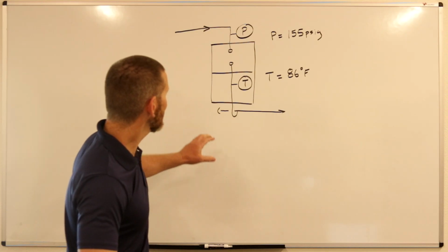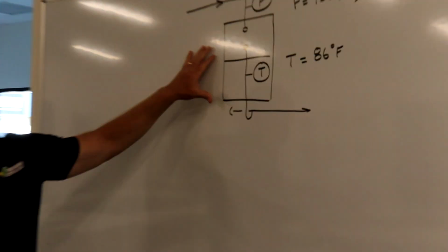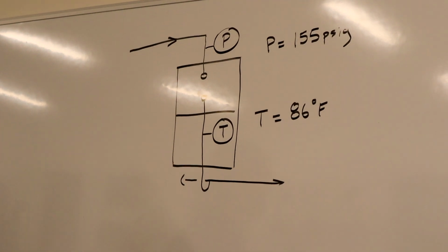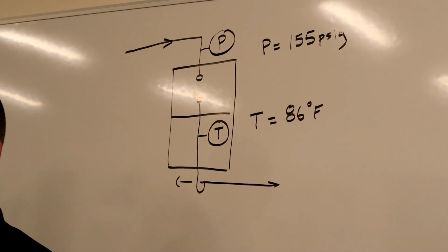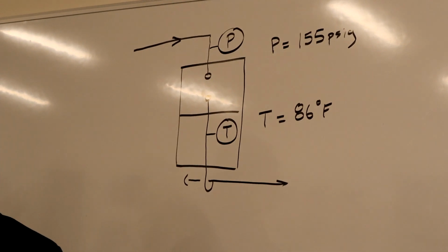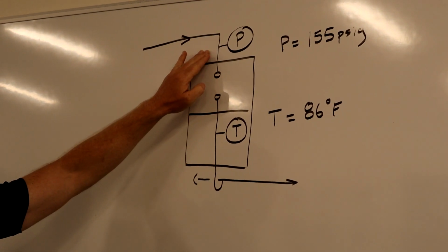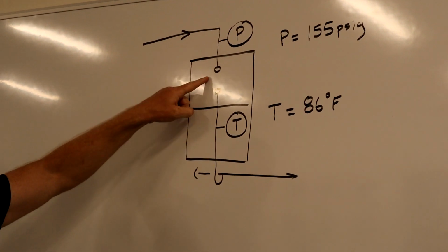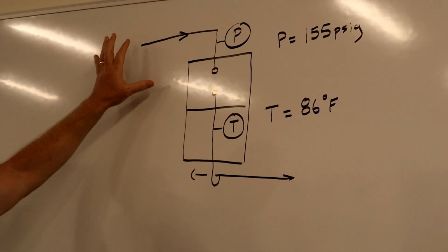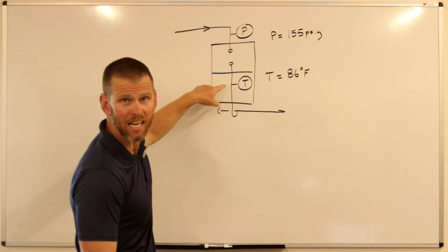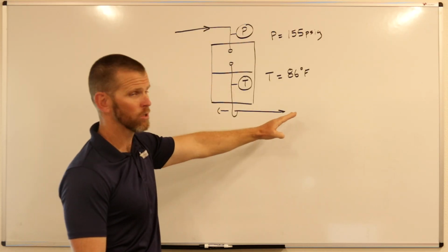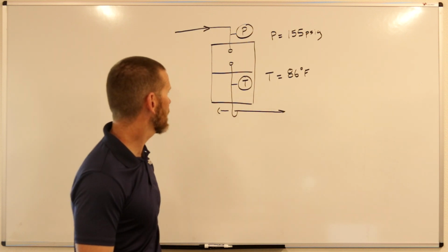All right, in this example, we have a condenser, and we're going to use our saturation tables to assess this condenser to see if we think there's non-condensable gases inside of it. So this condenser has discharge vapor going into it from the compressors. The heat's getting rejected to atmosphere. Out comes saturated liquid, which would drain to the high pressure receiver. That's what's being depicted here.